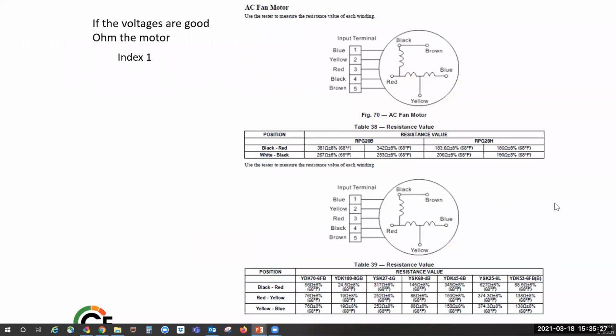Now, when you're reading these charts, they're in your service manual, and this is just a couple of examples because they do change per motor and system. You want to follow the colors. The 5-wire, of course, here is index 1. These readings are also affected by temperature. Between two of these, you aren't going to have any readings. So you want to follow your black, red, yellow, blue to yellow. You'll have to know which motor you have. If you can't see it on the motor, you can find it the same way you did the compressor.